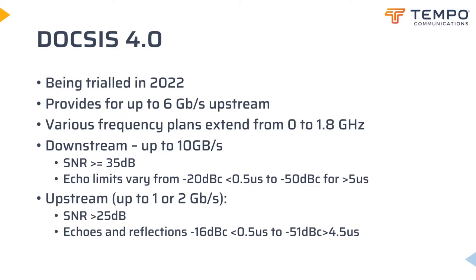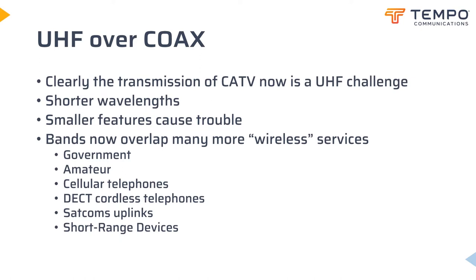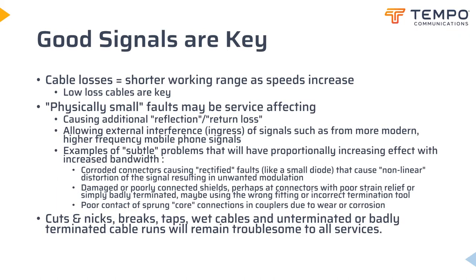UHF is the band from 300 to 3000 MHz, or 3 GHz. If you transform a signal to an electromagnetic wave using an antenna, these signals have wavelengths from 1 meter to 1 tenth of a meter. There are more sources of interference that can disrupt a signal, and smaller features on a transmission line can affect those signals. Signal loss over any particular length of cable increases as frequency increases. Smaller features and points of damage can lead to troublesome interference and reflection.